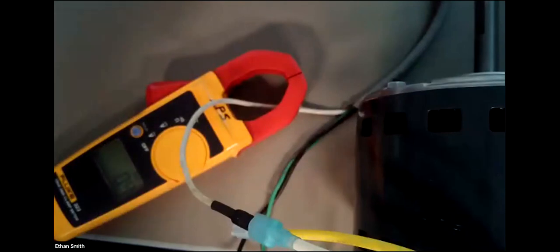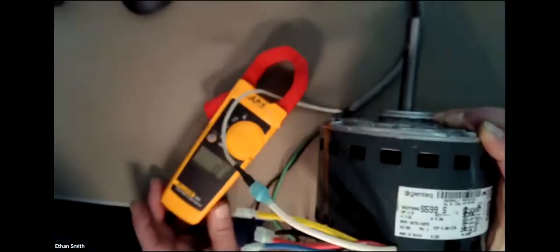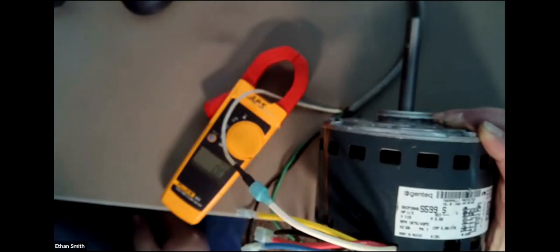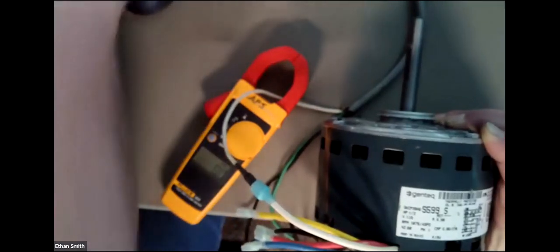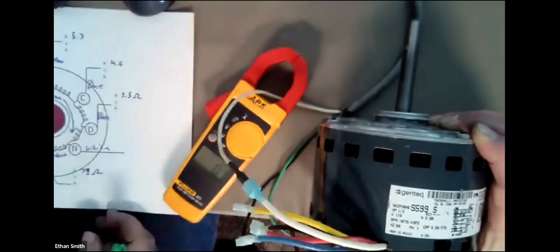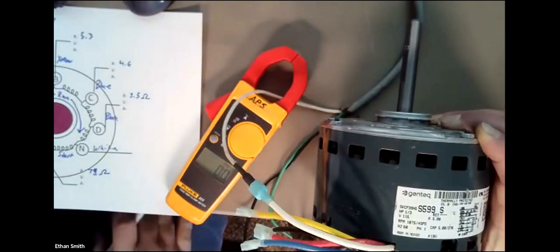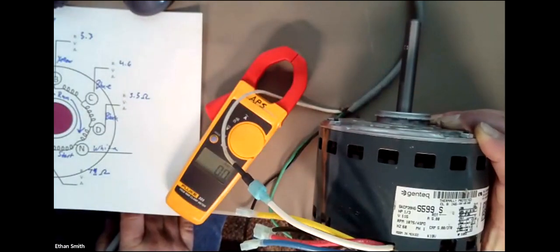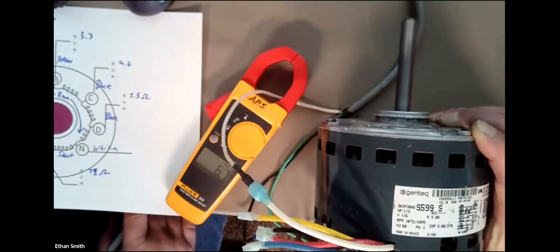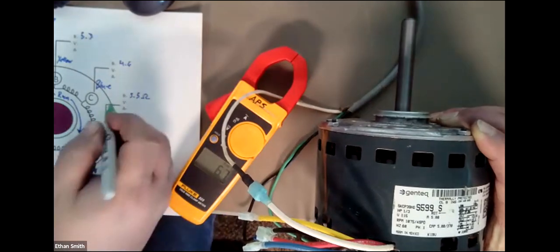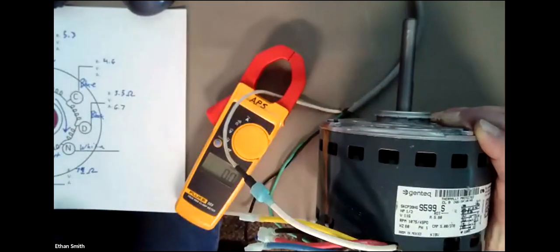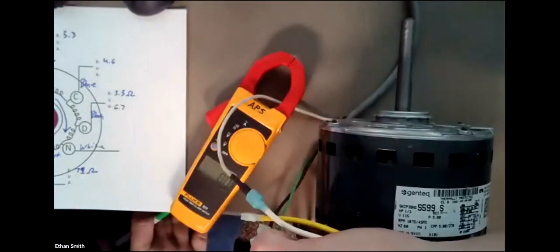And we're going to start with that black wire because that was our lowest, right? So low resistance should equal high current. So we're going to put our clamp on amp meter here. And we'll pull this out a little bit. Okay, there we go. I'm going to get another marker here. We'll record some amperages. So go ahead and start that up, Keith. Okay. So we got 6.7 amps on the meter. Pretty respectable for a 3rd horsepower motor.